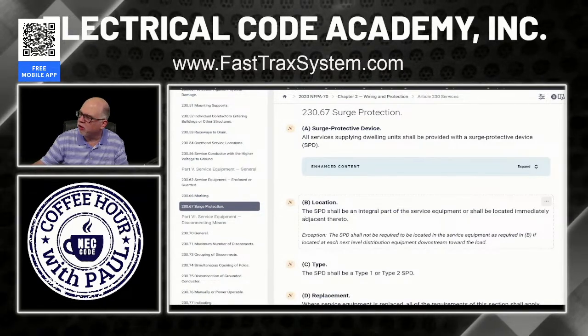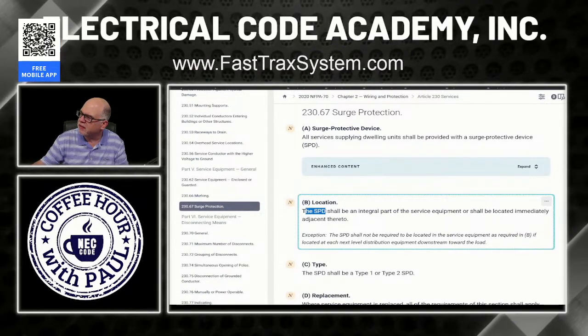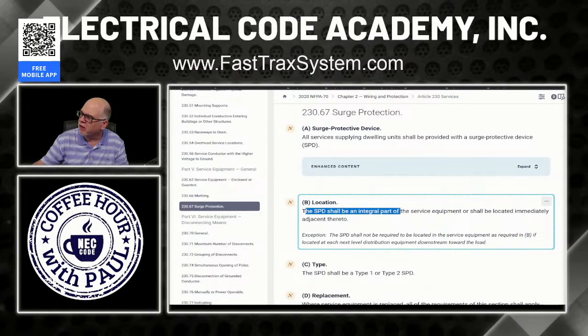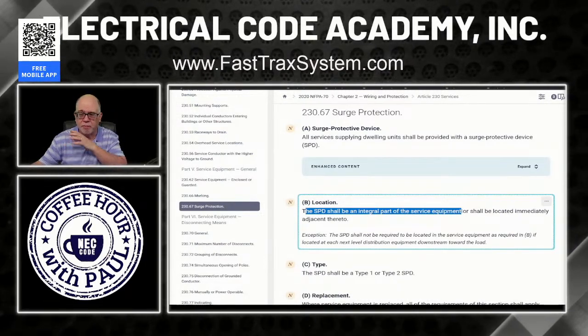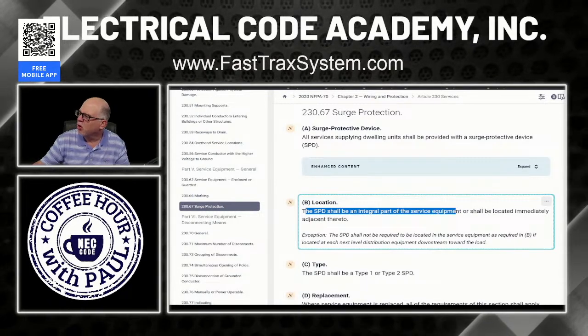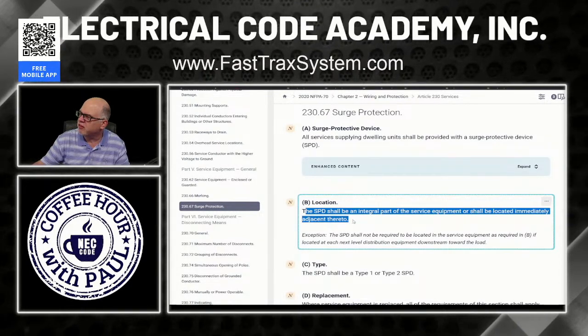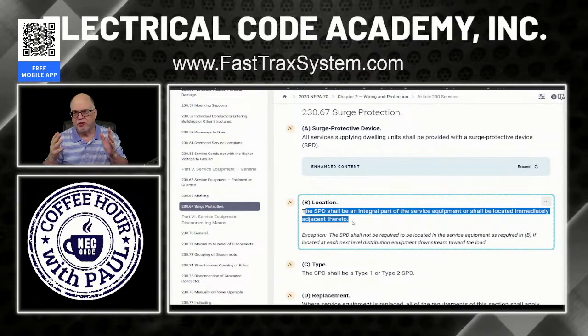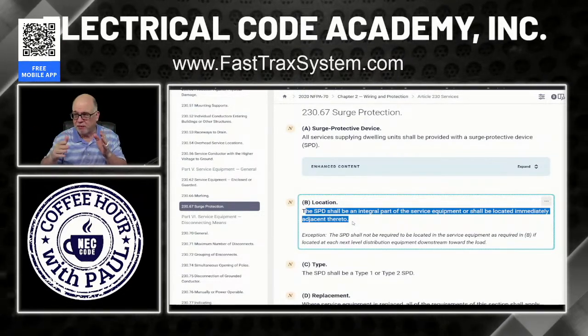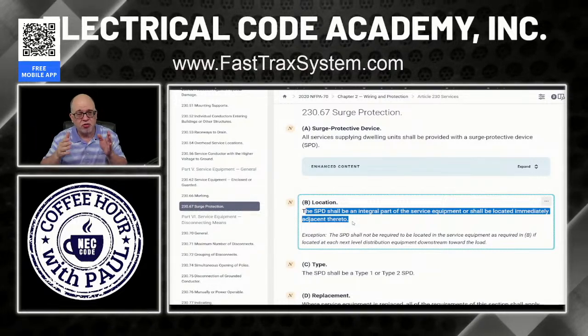As you saw in our language here, it says the SPD shall be an integral part of the service equipment, either right on the bus, a plug on the bus, or built into the equipment, or shall be located immediately adjacent thereto. So that means some of the ones that you see for services, now this is not just for multifamily, right? This applies where? All services, okay?